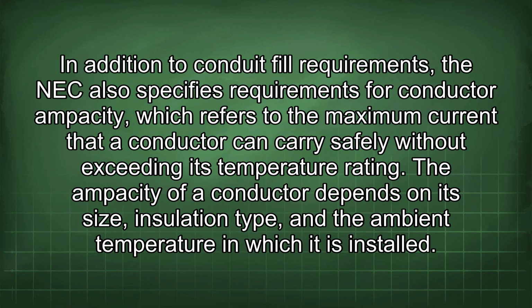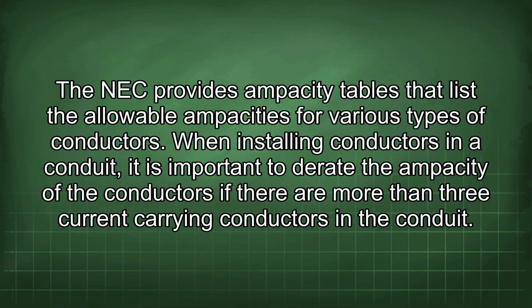In addition to conduit fill requirements, the NEC also specifies requirements for conductor ampacity, which refers to the maximum current that a conductor can carry safely without exceeding its temperature rating. The ampacity of a conductor depends on its size, insulation type, and the ambient temperature in which it is installed. The NEC provides ampacity tables that list the allowable ampacities for various types of conductors.